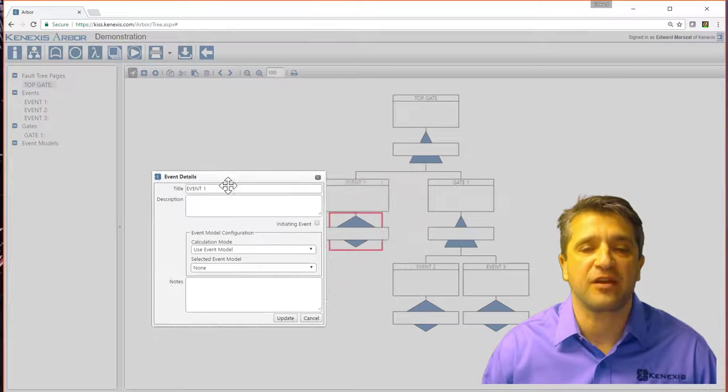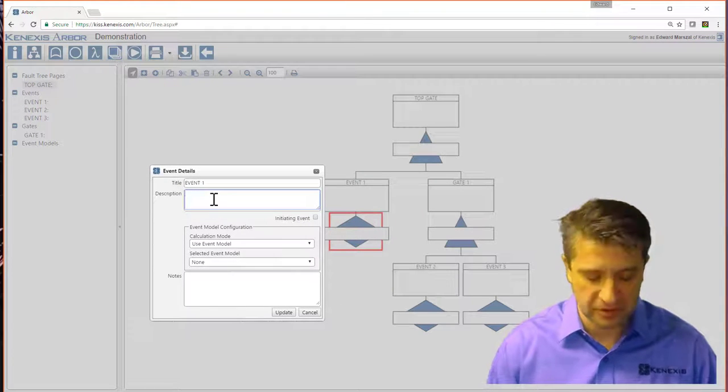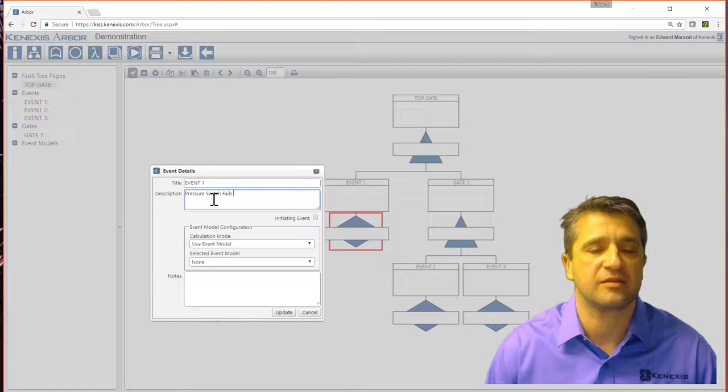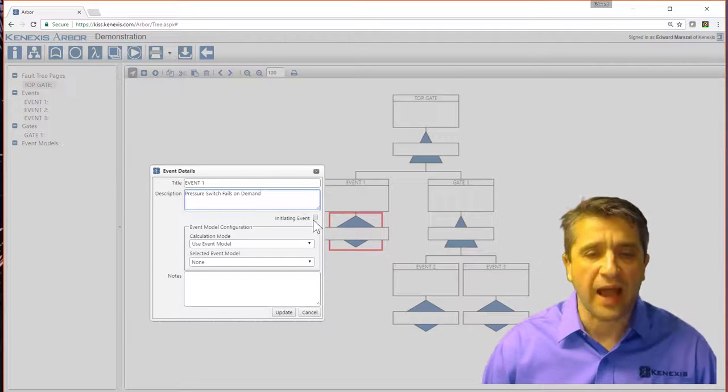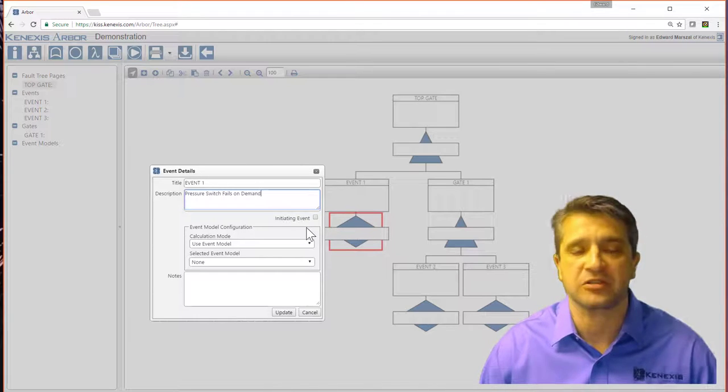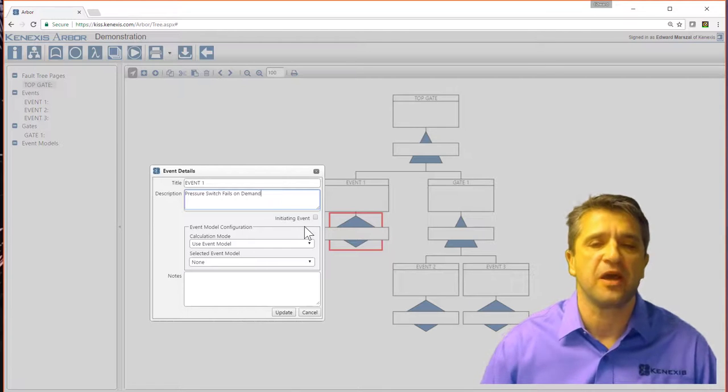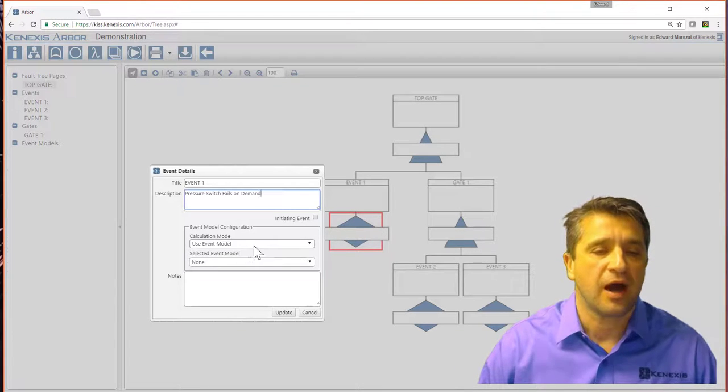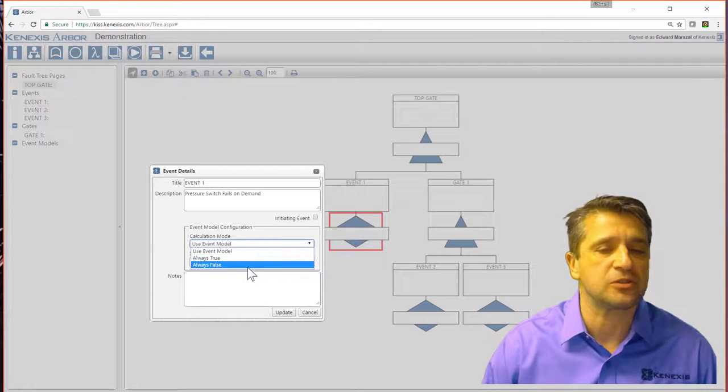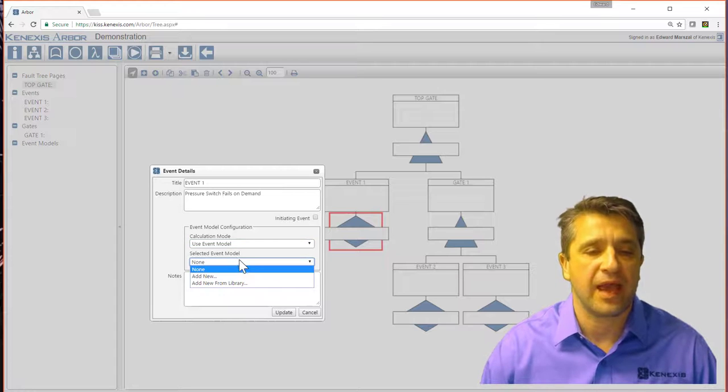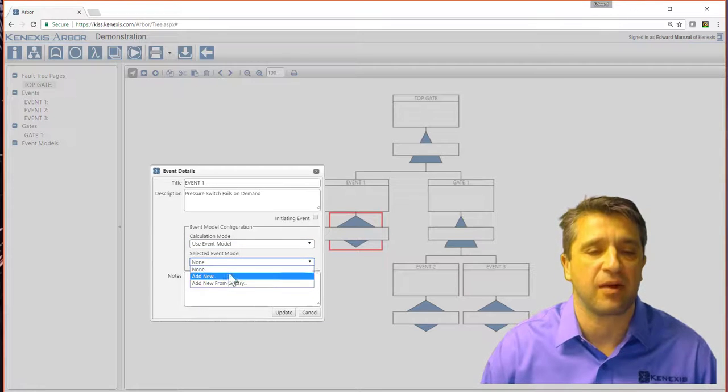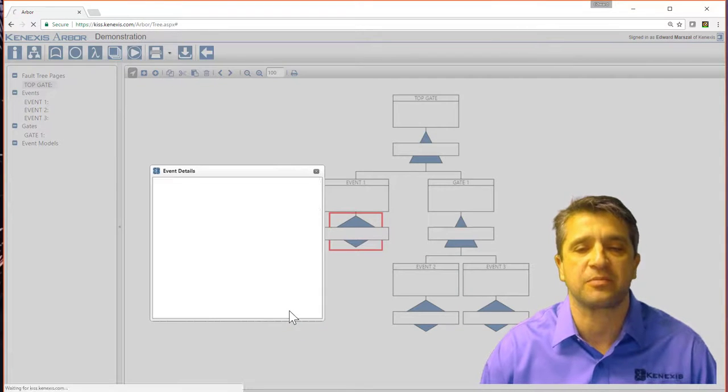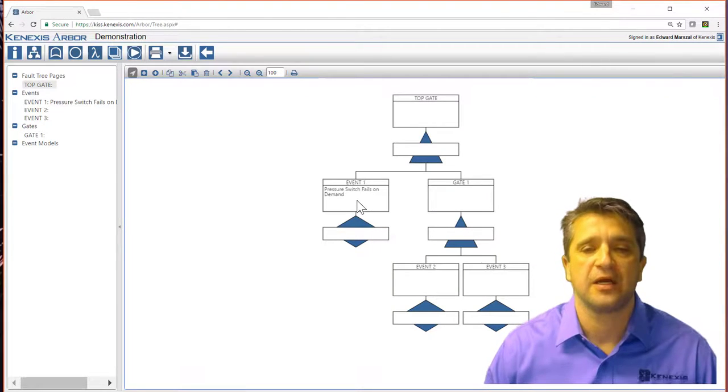For event number one, the description, let me say pressure switch fails on demand. I can make this an initiating event or not, which is not important for SIL verification calculations, but in general purpose, it does become important. The calculation mode, I can make it either always true, always false, or I'm in this case going to use an event model. Let me just hit update for now and build out the structure of the tree.